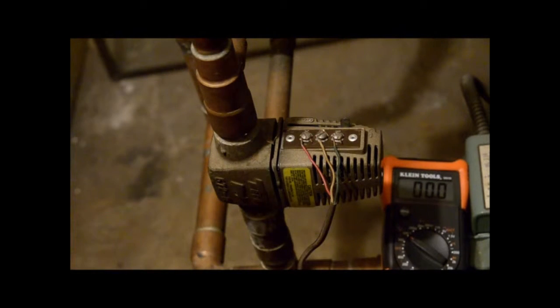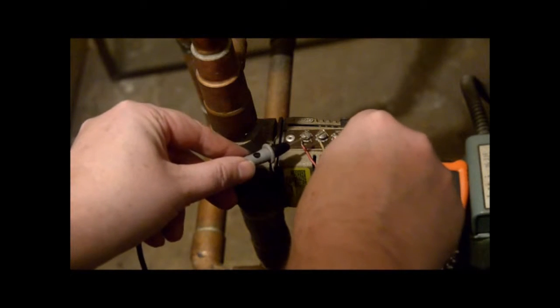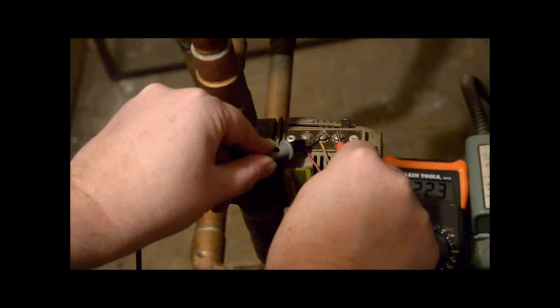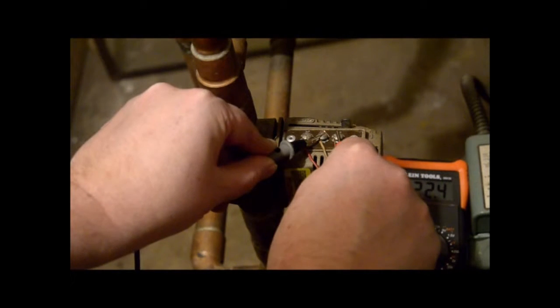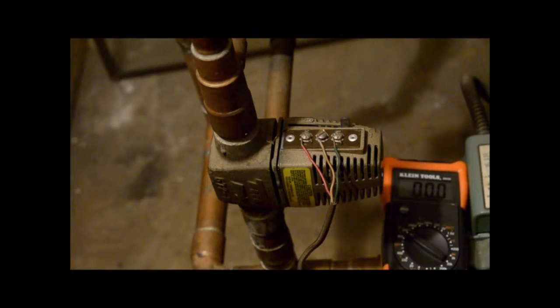I'm going to turn on the thermostat. Let's check the voltage now. Yep, there's voltage, 22.4 volts. So that's telling us that electricity is going there. At some point here, the valve will open up, and then we'll see 24 volts.